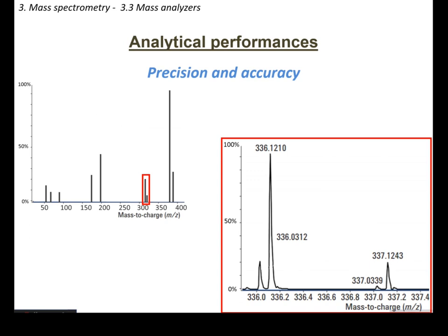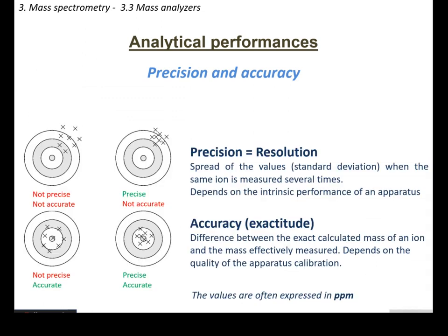If you look at a mass spectrum from far, let's say, you will see these little vertical sticks. But if you zoom in, maybe you will see a bush of peaks, in fact. Remember that before making centroid transformation, the signal is continuum. And so it means that you have curves there. And if you zoom in, you can see maybe a very good separation of different masses. So this is the case, of course, only with high-resolution mass spectrometers.